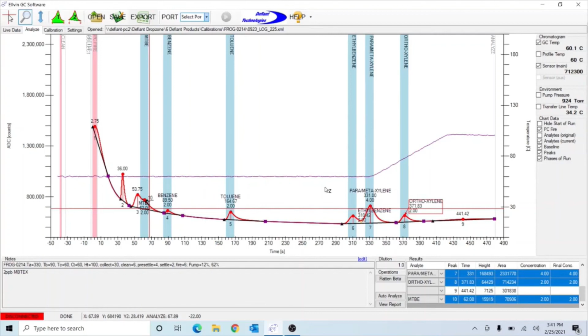The responsiveness of the detector does change over time. That's because the detector gets dirty. So how often do I need to do a calibration? Well, it depends on you. The more you use it and the higher concentrations that you're looking at, the more frequently you need to do your calibration. One way to check this is to run a known sample. Usually we recommend you do a midpoint, so I could do a known concentration of 16, analyze it, and then look and see how close I am to that 16 with this calibration. That will tell you how often you need to do calibrations for your operation.